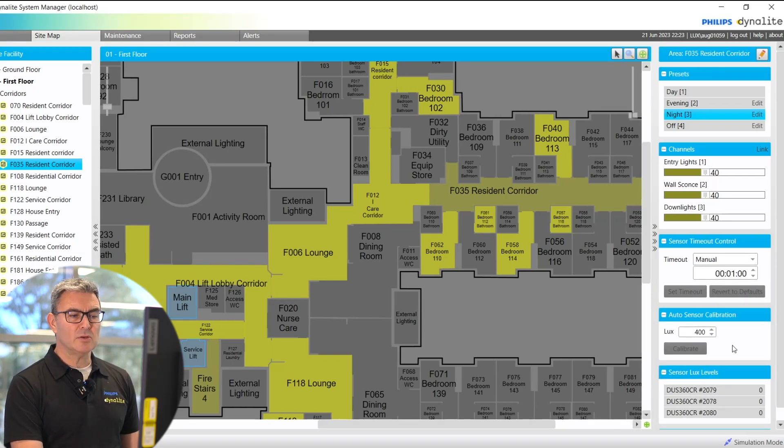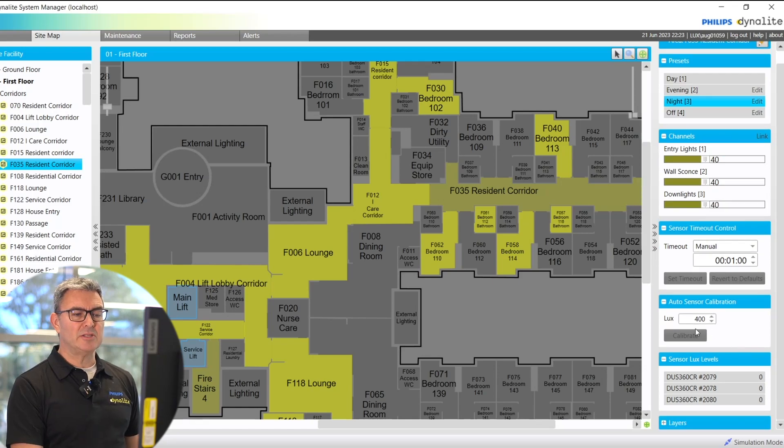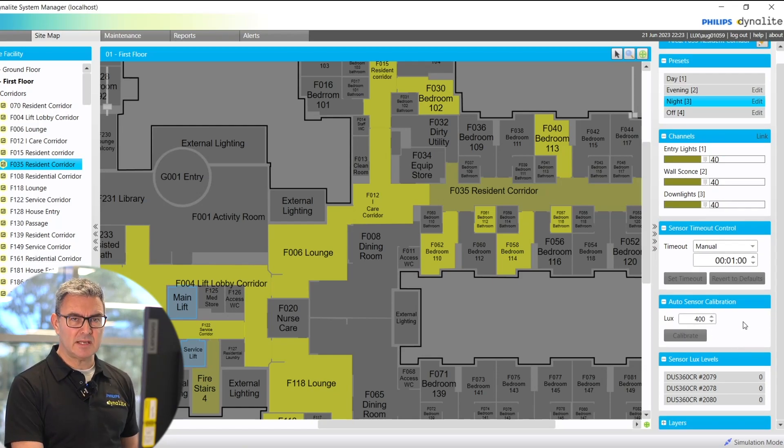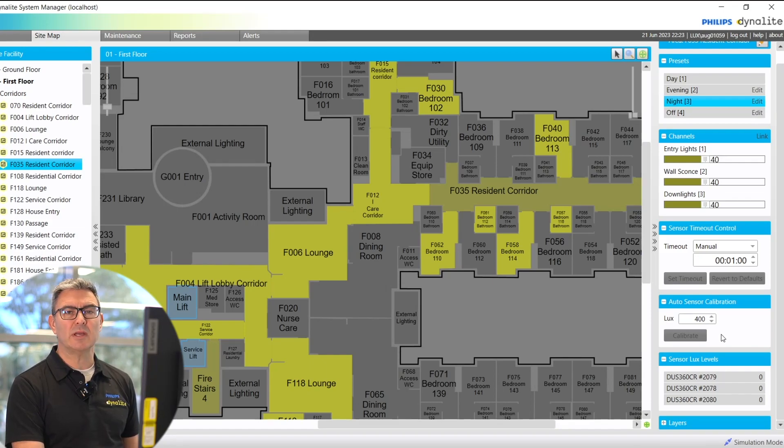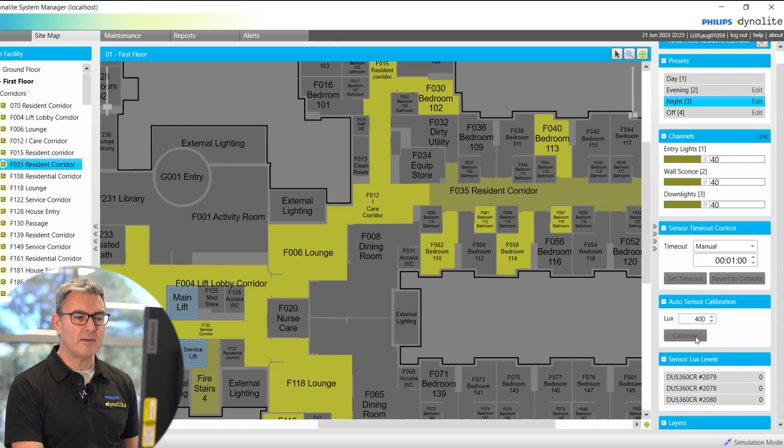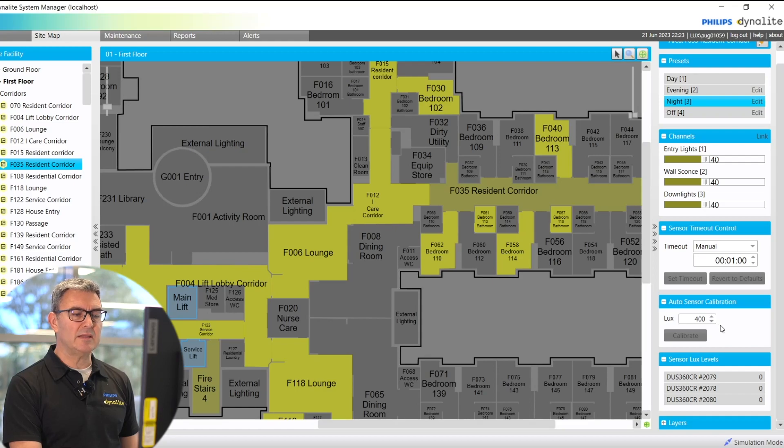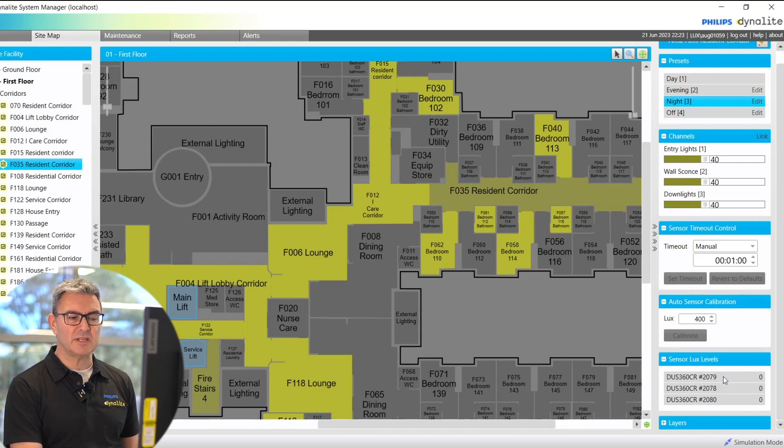I can auto-sensor calibrate, so I can put a value into here, take a lux meter, take that measurement, put it into this field, and then it will calibrate all the sensors in the area. And I will get a display here of the actual sensor lux levels.